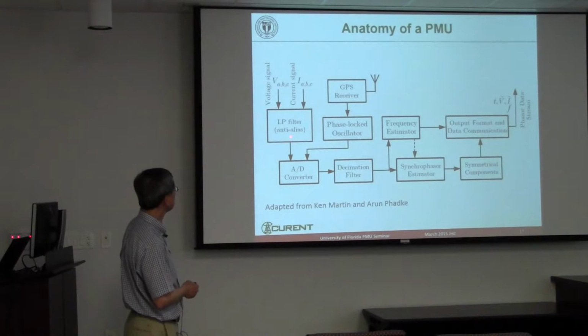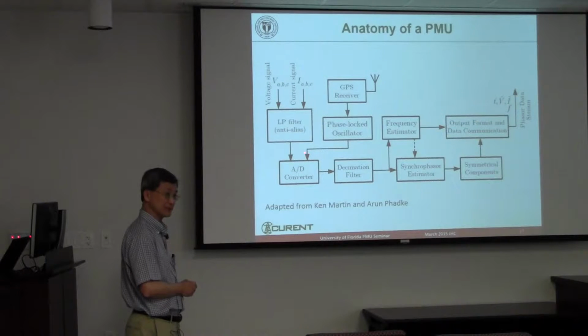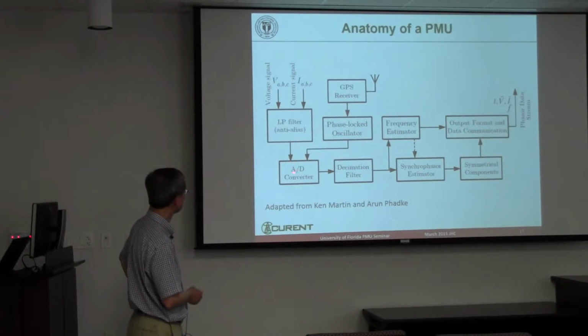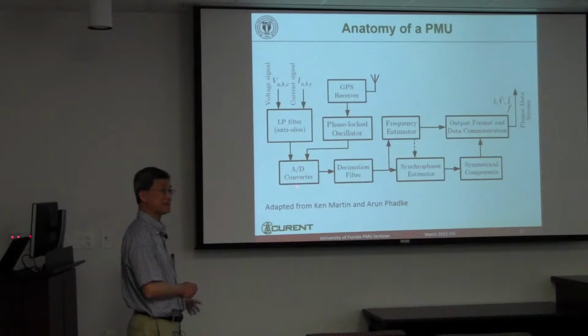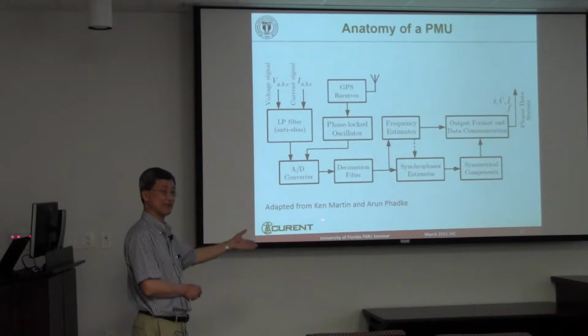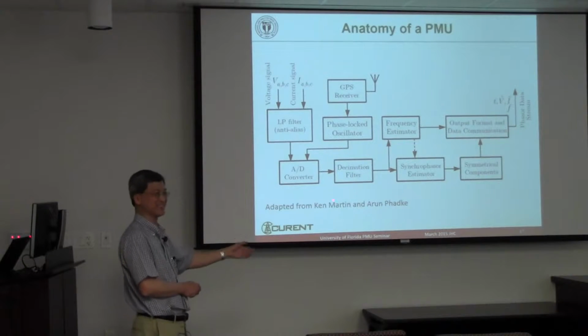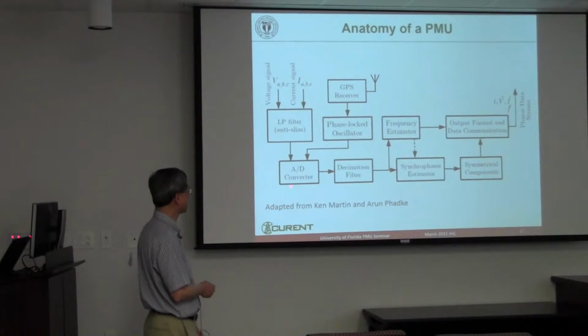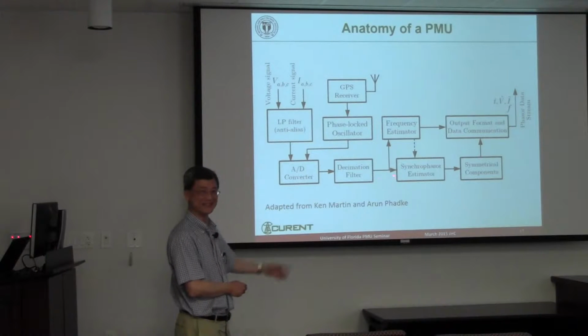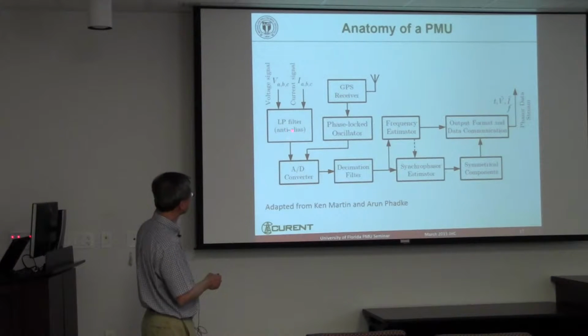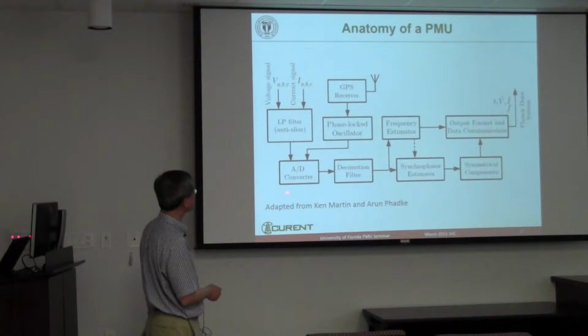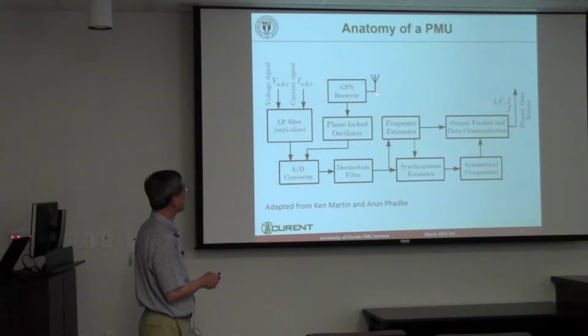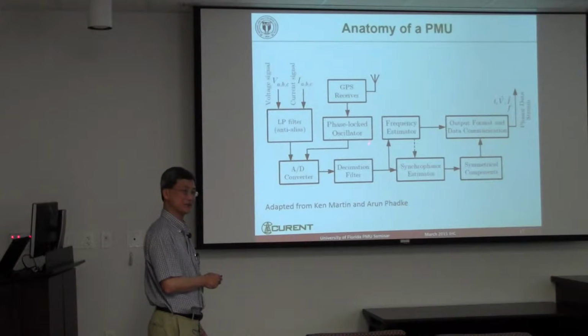So you take the signal, you do the anti-aliasing filter. This is still analog. And then you have to do an A to D conversion. Again, power people are pretty cheap, so you multiplex. There's only one A to D converter, which can be the most expensive component in this thing. So you sequentially sample all the channels. And then you have a GPS signal to timestamp the measurement.